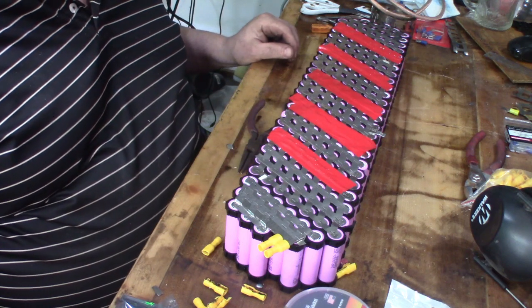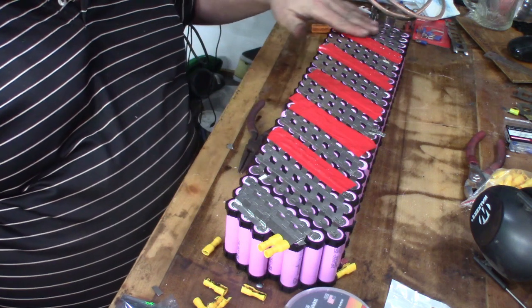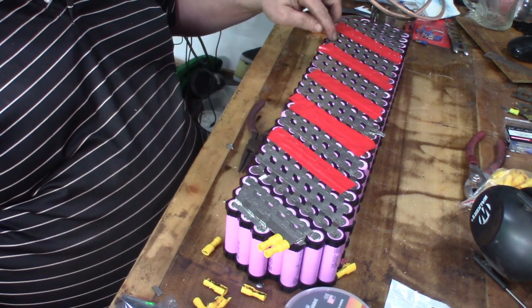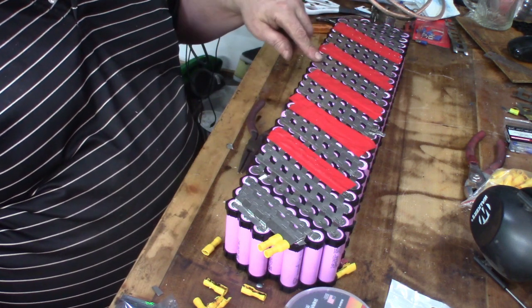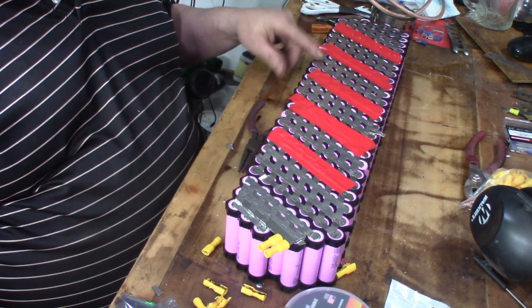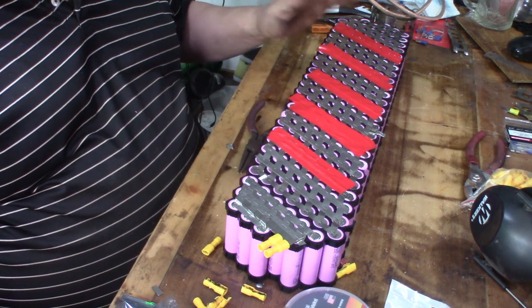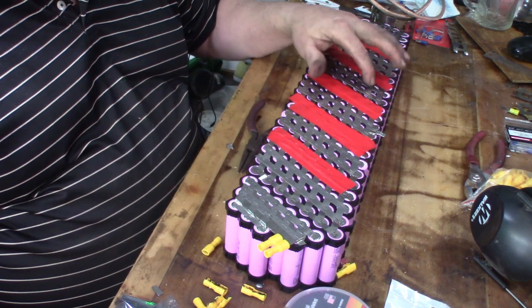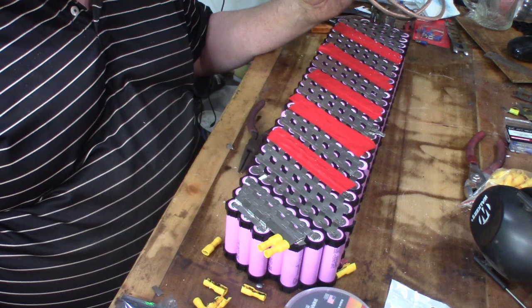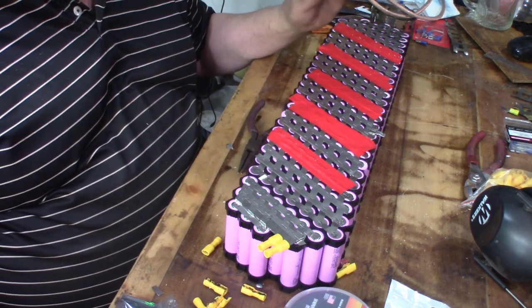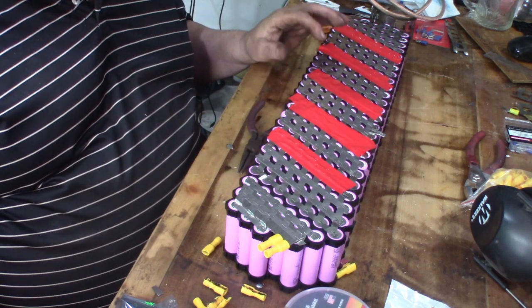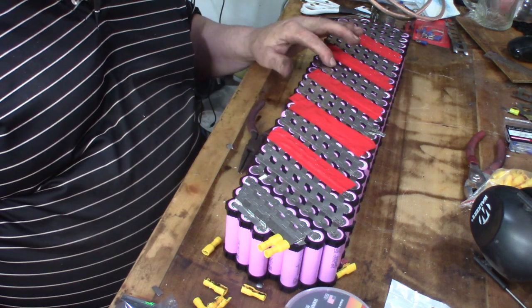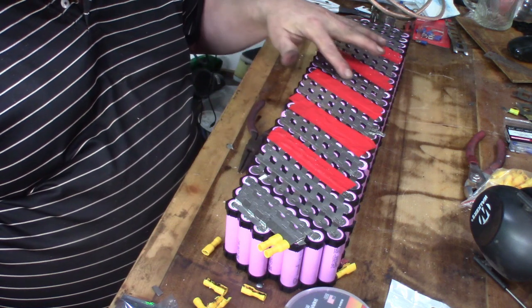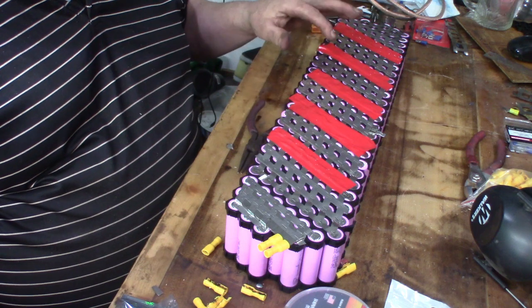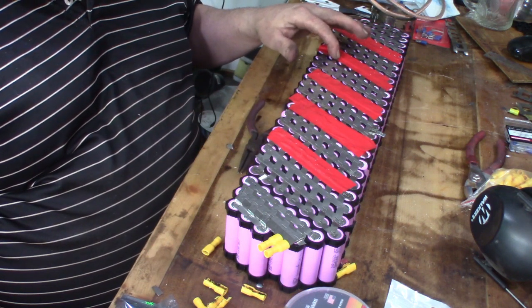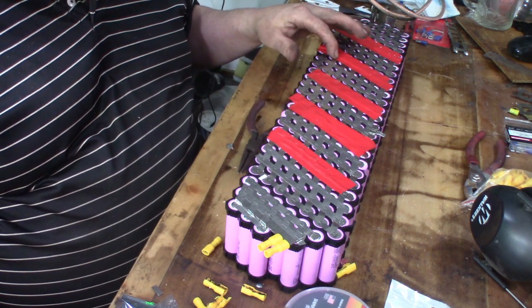And the series connections are done. Remember, with the series connections you have to make sure I've got 7 spaces. It has to be able to take the power from one full parallel pair. So each cross member would have to handle 112 divided by 7, which gives you 16.7 or so. But because the acceptable amount is 9.6, I had to put on 2 layers across the series connections. I don't have to do that with the parallel connections, because across those it's at most 8 amps.